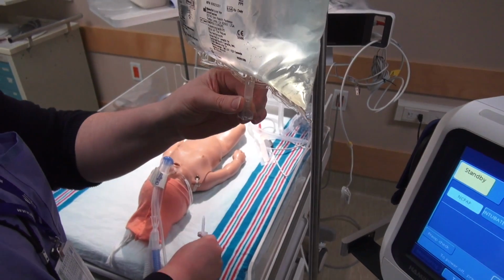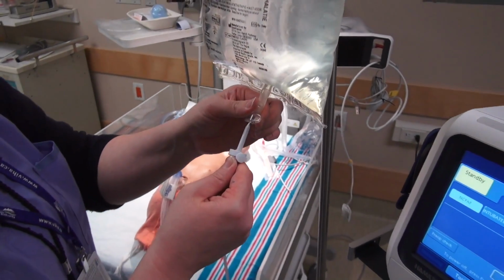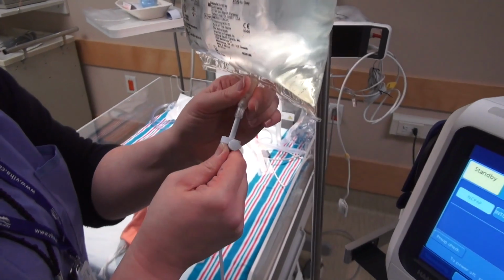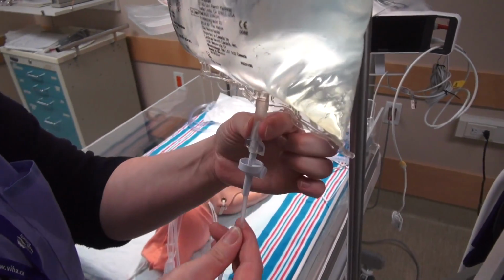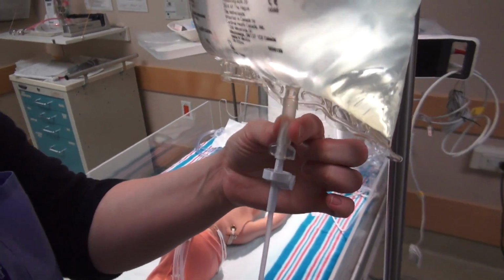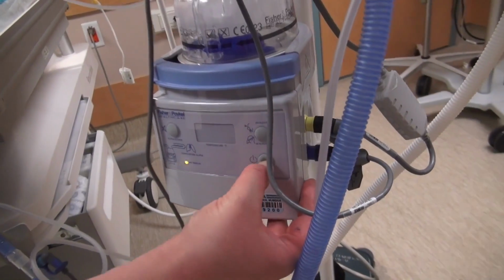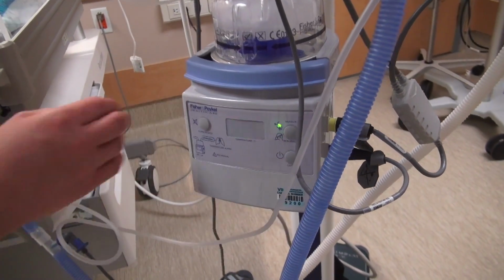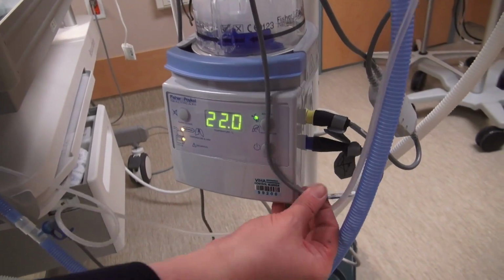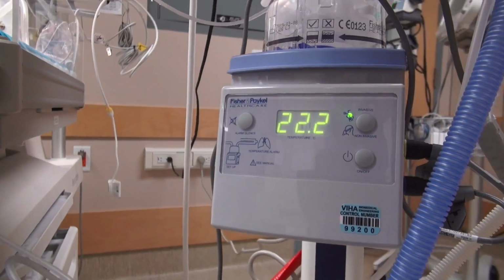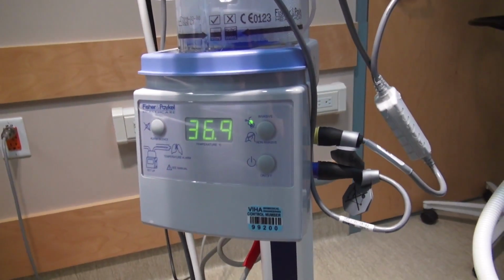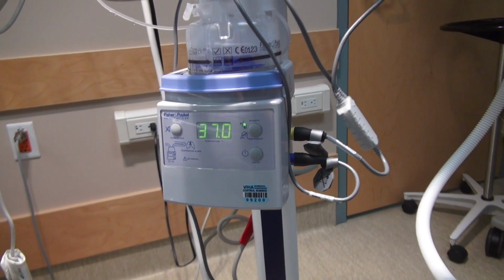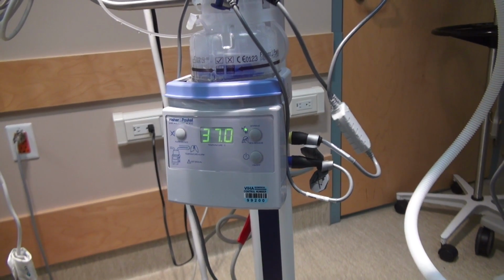Step 6. Spike sterile water for inhalation bag with spike from humidifier chamber, if not already done. Step 7. When ready for use, turn on Fisher-Paykel heated humidifier. Default settings are set to invasive at 37 degrees. This is what it should be set to for both nasal CPAP and ventilator mode for the neonate.